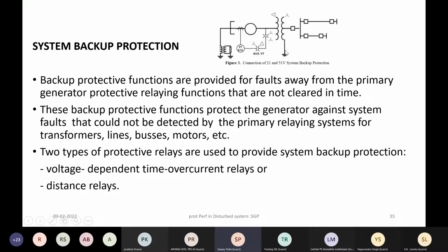Especially the inverse time coordination becomes sometimes very difficult to achieve, because the fault current seen by the overcurrent relay on the line and the overcurrent relay here would be almost the same. Moreover, if there are a number of generators in parallel, then this neutral current due to system fault gets shared with all the generator transformers' neutrals. So this current sometimes may not be sufficiently sensitive. So the setting of this overcurrent relay, as well as the time coordination with the line protection, is critical to maintain the proper coordination and avoid the undesirable tripping.